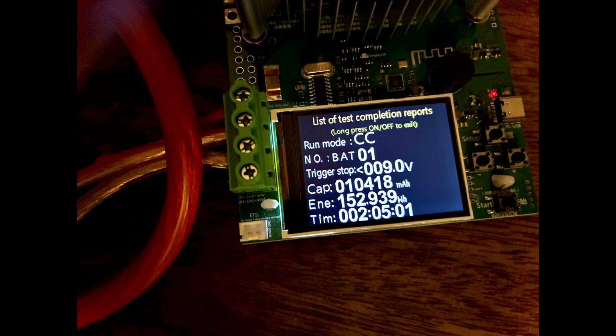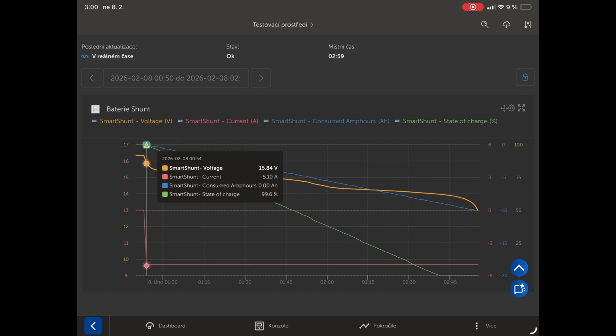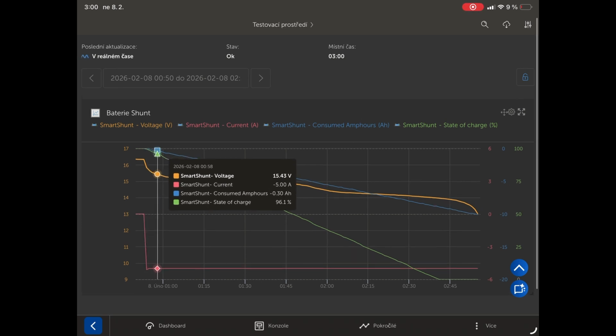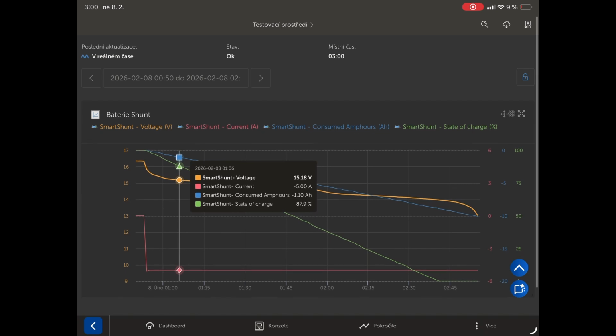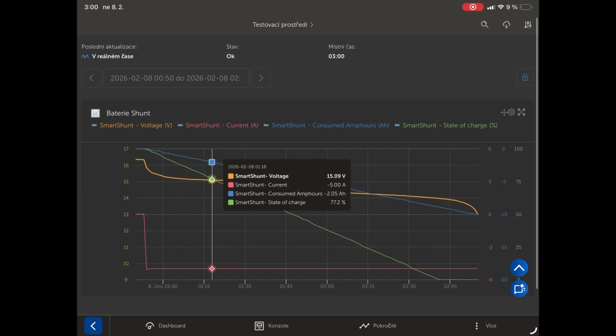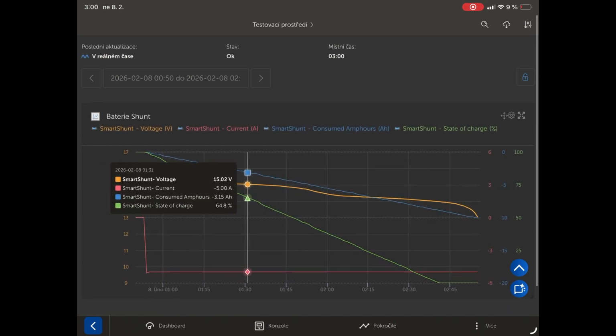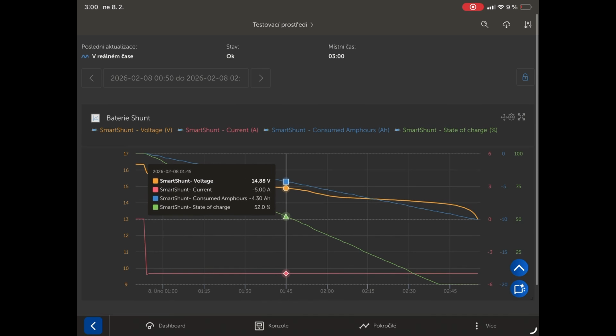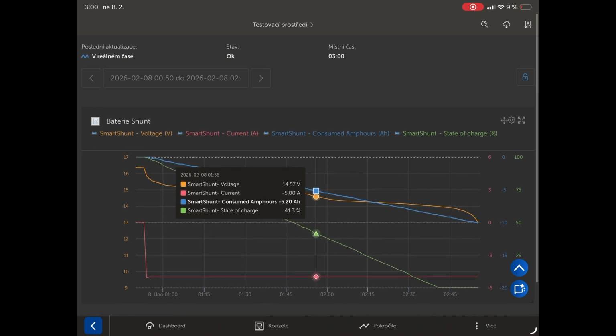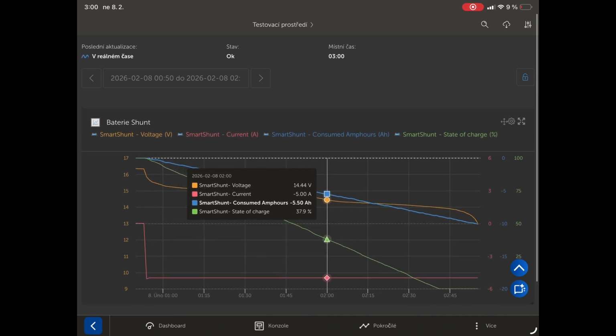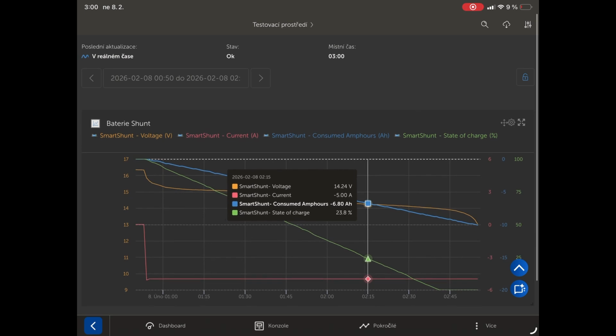The battery generated 10.4 ampere hours and 153 watt hours. Here we see the discharge curve for the 6-cell battery. In the graph, you can clearly see how stable the discharge curve is for this 10 ampere hour battery with a constant 5 ampere load.